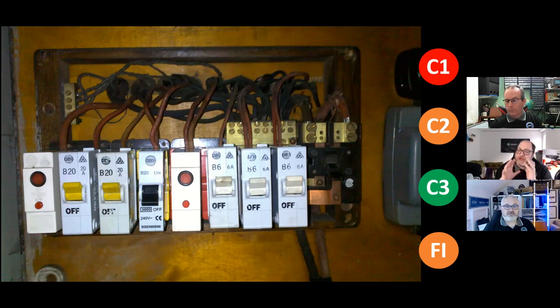Right. So it's not worth it? Okay, so you've made an initial observation that the switchgear is life expired. Yes, but also the cabling is potentially life expired, because I can see that the cabling is flaking and fraying. I don't want to bring a risk of danger to that installation by interfering or touching it. So at that point you're going to put a C2 in. Yeah, which is not immediate remedy, but is still unsatisfactory. And you're going to stop doing your inspection at that point.